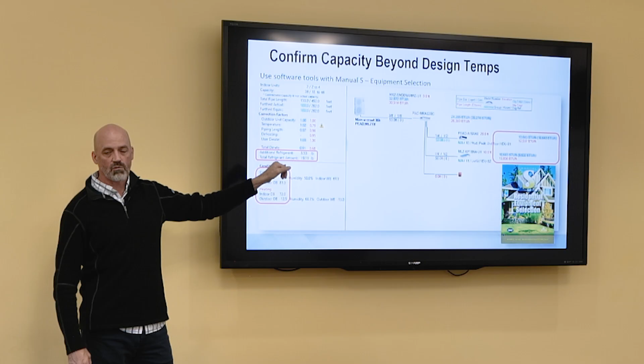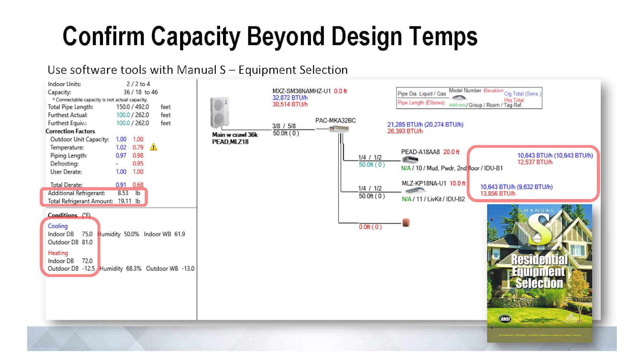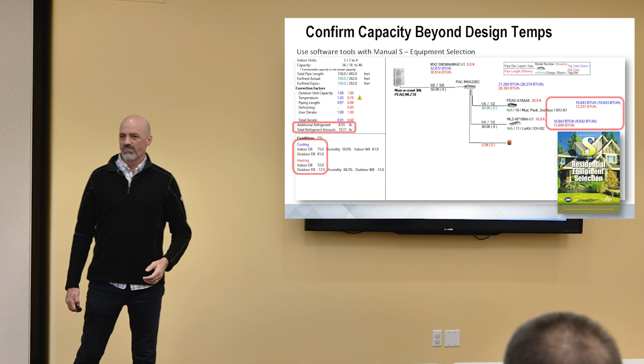There's also the design conditions. So these numbers are by design for the conditions up here. It's altitude. And in fact, these derates right here, these correction factors, deal with temperature, piping length, defrost cycling, and what you don't see in here is actually buried in this 0.68 derate is altitude as well, right? So it does all the math for you properly, because doing that longhand is a pain in the butt. I don't want to do that, no one does. So we think about double-checking the specs on the equipment. We use these design parameters, but we have to pick the right pieces of equipment, the right model numbers. These two pieces of equipment are one to two digits off on the model number. They're really close. It's easy to miss.